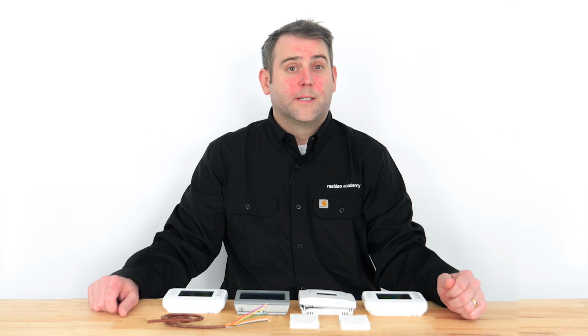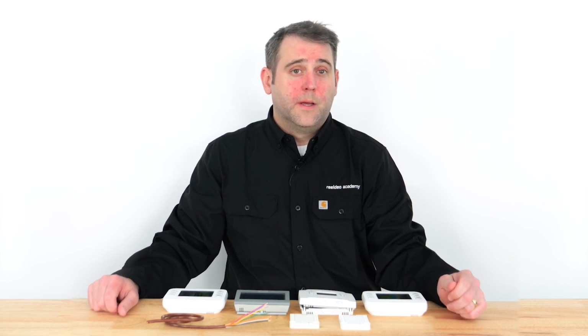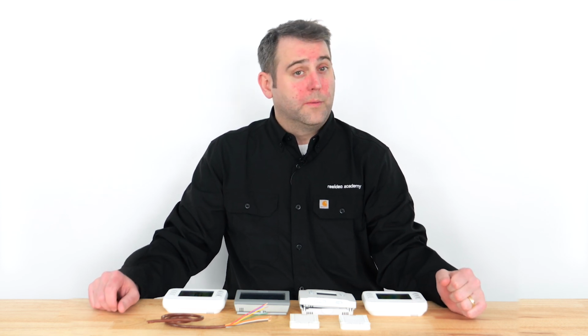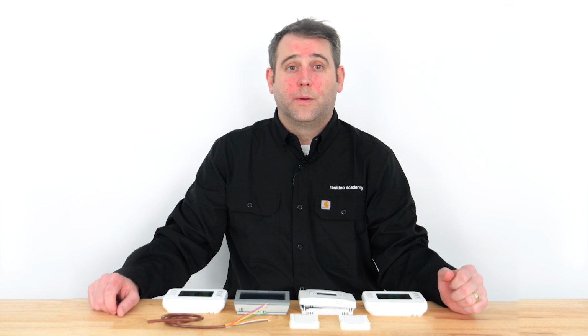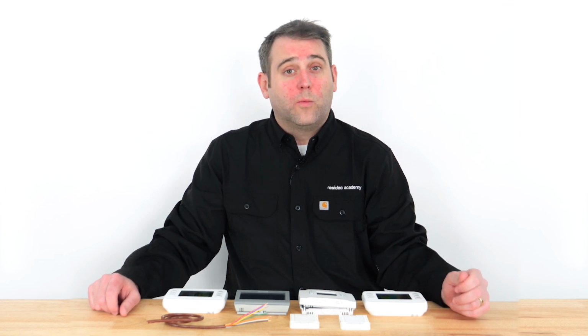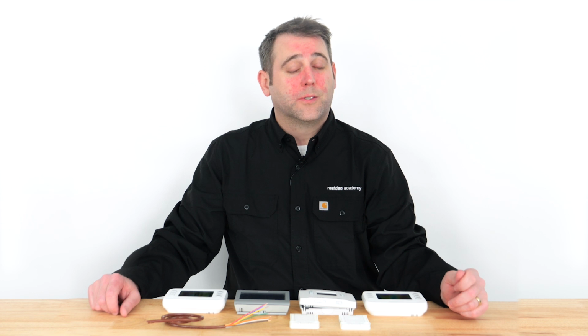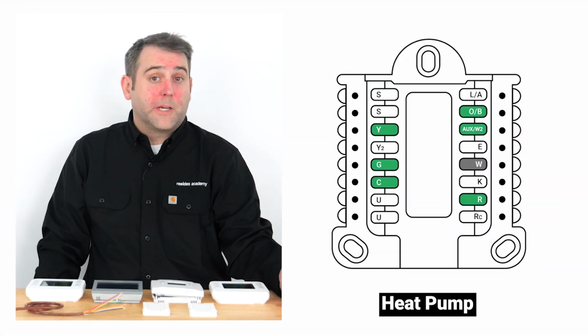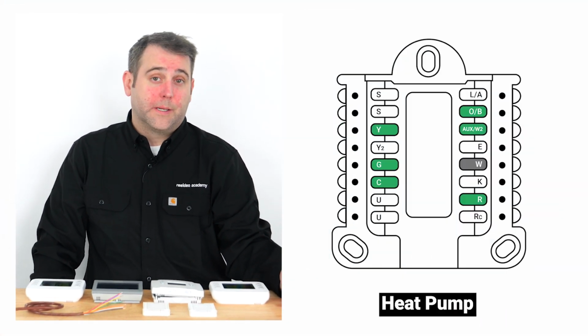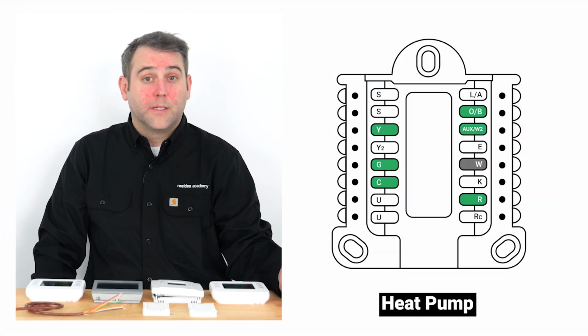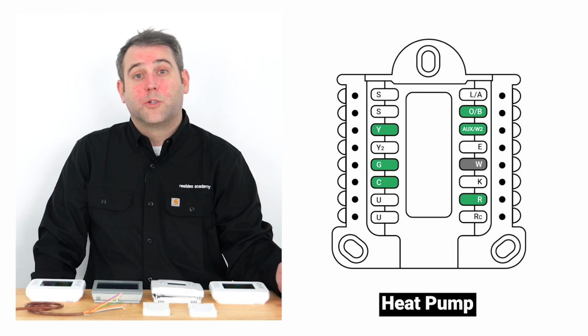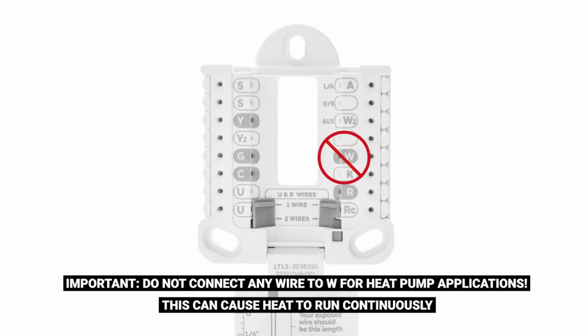Problems 5 and 6 have the same troubleshooting steps. So, if heat is running when cool should be, or cool is running when heat should be, or if your heat or cool simply won't shut off at all, incorrect wiring or configuration is most likely to blame. This is especially crucial if you have a heat pump system, when the heat is running continuously even when the system should be cooling. Remember, do not connect any wire to the W terminal for a heat pump application, as this can cause the heating to run continuously.